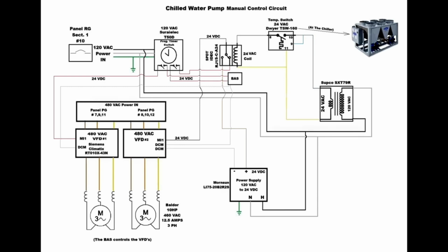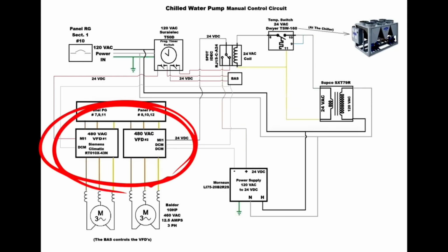And what we did, again, everything's still controlled by that programmable digital timer, still have the safety switch at the chiller, but now I simply installed a power supply, and it's 24 volt output DC, because the VFD input control terminals are 24 volt DC. And so basically the way this works is when the building automation system is calling for one of the pumps to turn on, that 24 volt signal from the BAS doesn't go directly to the VFD input terminals. It goes to our programmable digital timer. And if the programmable digital timer says, yes, it's the right time of day to allow the pumps to run, then that signal will go through to the VFDs, and the VFDs will turn on the water pump.